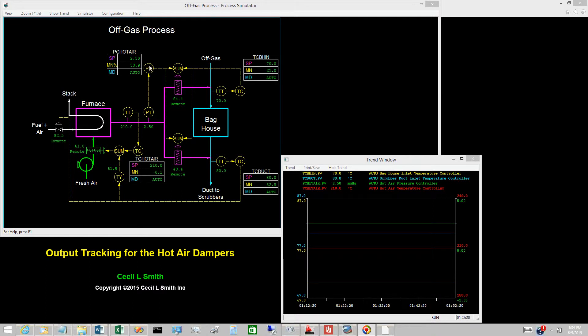The output of the hot air pressure controller is the arithmetic average of the opening of the two hot gas dampers. When this controller is tracking, the analog value for output tracking must be the arithmetic average of the current openings of the two dampers. The output of the baghouse inlet temperature controller is the difference in openings of the two dampers. When this controller is tracking, the analog value for output tracking must be the difference of the current openings of the two dampers.